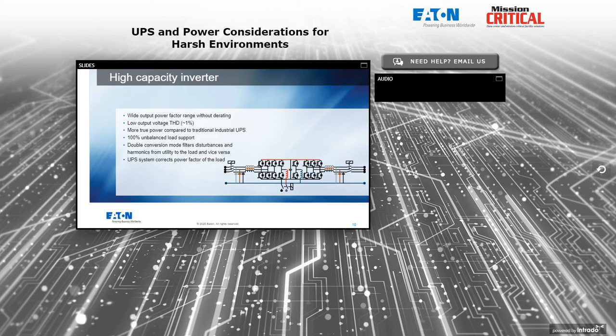More kilowatts or a higher output power factor compared to a traditional industrial UPS, which might still be rated for 0.7 or 0.8 power factor. The ability to handle unbalanced loads, sometimes severely unbalanced loads. Modern transformerless UPSs should be designed to take as much as 100% on any phase, regardless of the percentage on the other phases, and handle a high unbalanced current. Remember, though, that if you exceed 100% on any of the three legs of a three-legged UPS, you are going to get an overload alarm, and the UPS is going to take action to transfer to bypass, even if the other two phases are not as heavily loaded as the one that's over 100%.